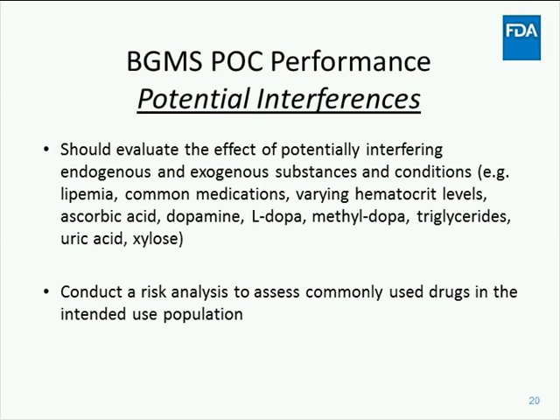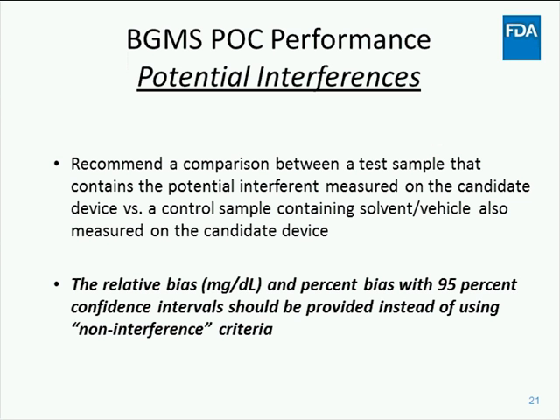This analysis should take into account device technology, the intended use population, the intended use setting. Any relevant potential interference should be included in the testing. The study design for these studies is not really all that different from what we see now, but there are a few differences. Similar to what we see now, it is recommended that a comparison be made between a test sample that contains the potential interferent measured on the candidate meter and the result of a control sample containing a solvent or vehicle, also measured on the candidate device.